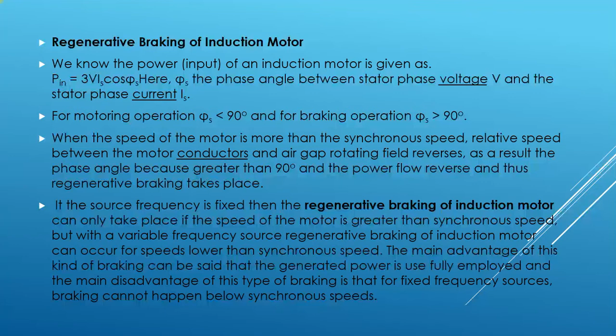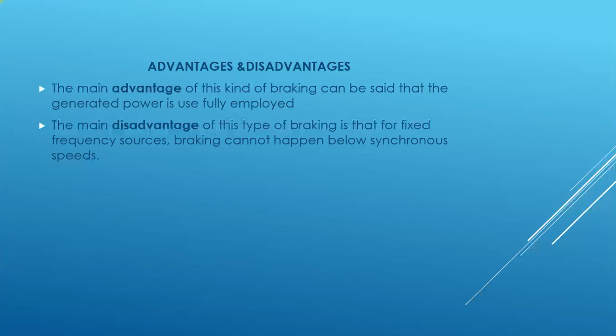And the advantage is that the generated power is usefully employed. As I already repeated, the main disadvantage of this braking is the fixed frequency source, so that the braking cannot happen below synchronous speed. So these are some types of braking methods which are employed in three-phase induction motors.